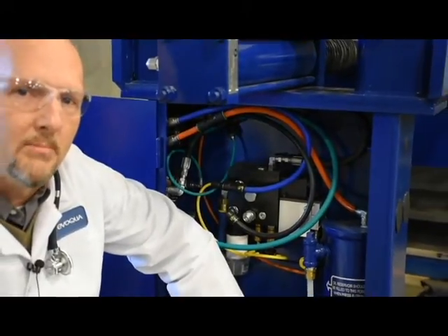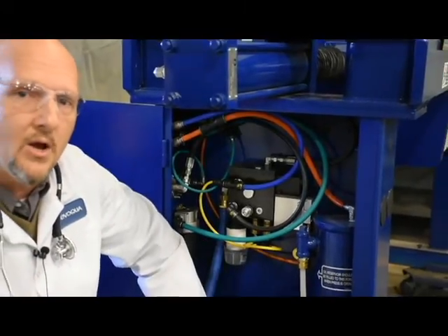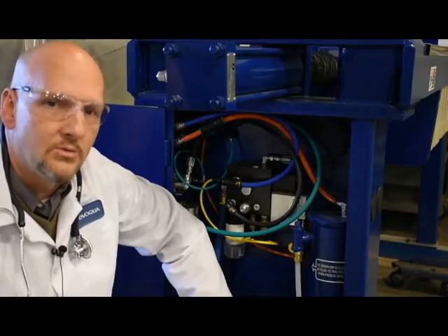Now a couple other reasons why your pump might be still running. There's a regulator here to regulate the air and that's how we initially set these pumps up. Now if that's set too high, it might continue to run as well.